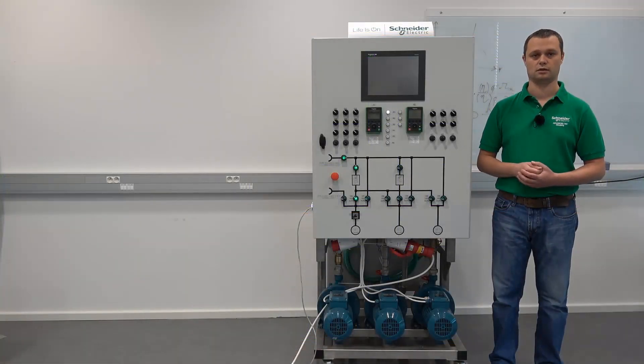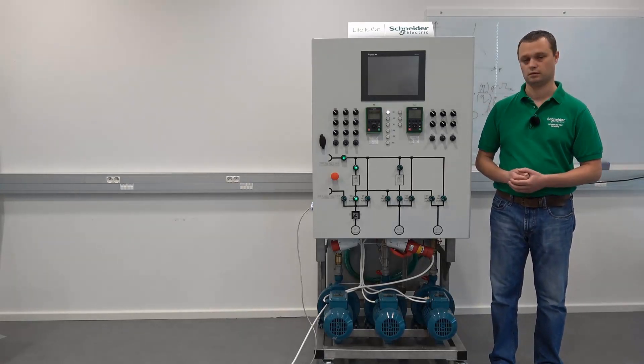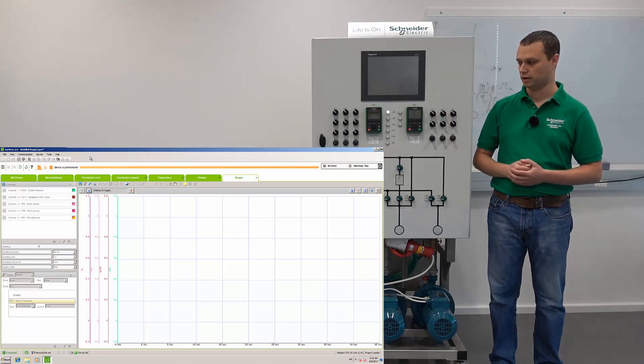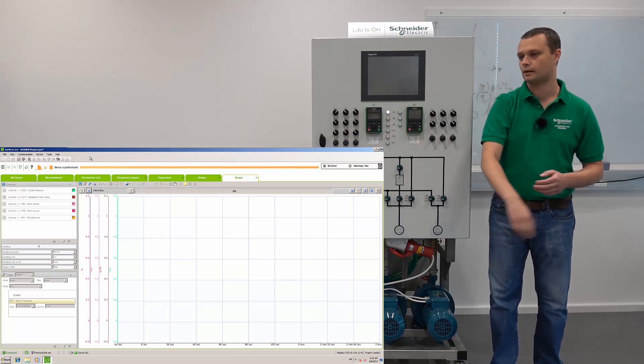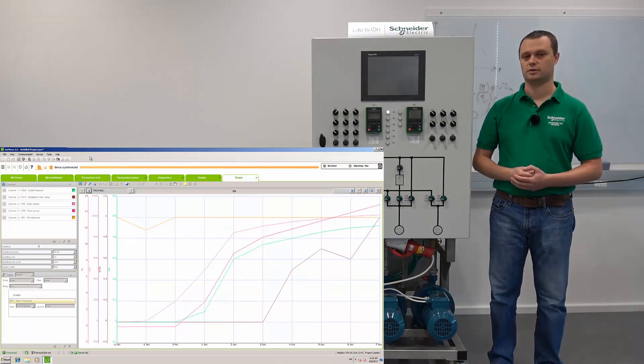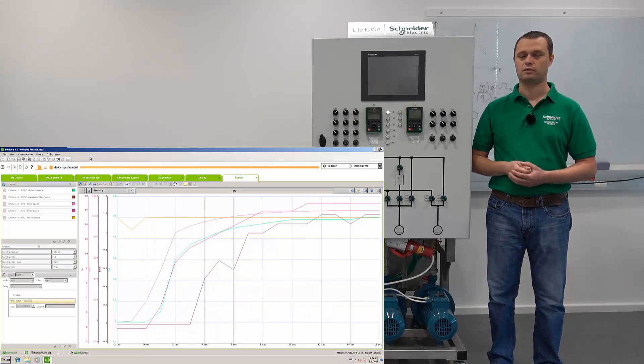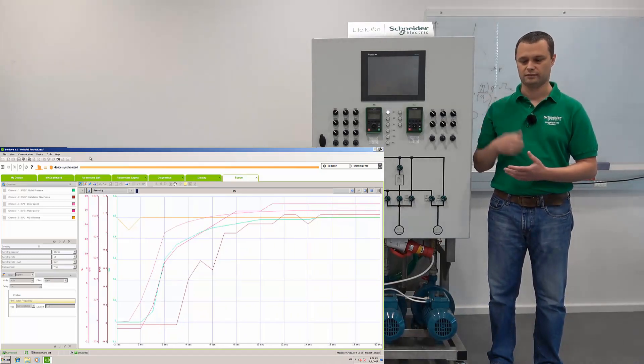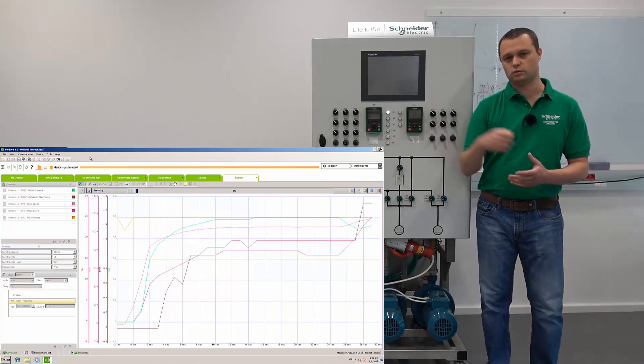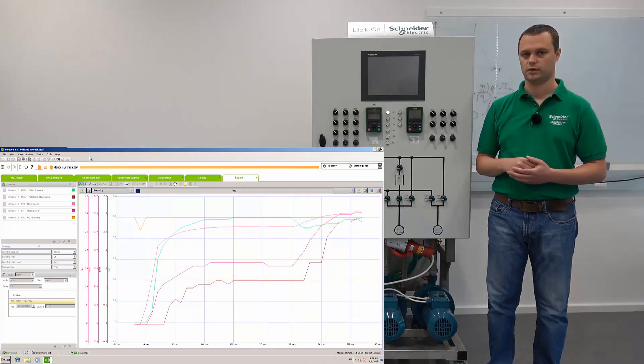We continue with our practical demonstration in front of the pump demo bench — everything is set up. We start the drive with logical input 1. You can see the scope trace in parallel. The drive ramps up and PID starts to work, keeping the pressure setpoint at 0.5 bars. Flow is not very high at this moment, so we simulate additional flow request by opening the valve. Flow starts to go up — there is a slight decrease in pressure but the drive compensates — PID is working.